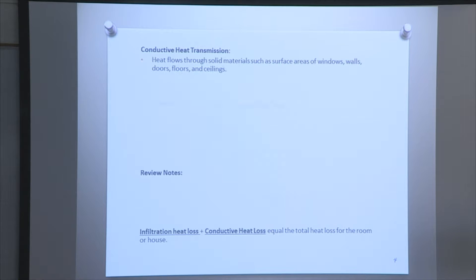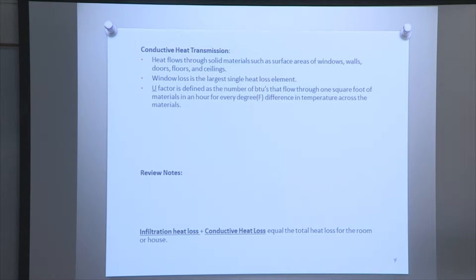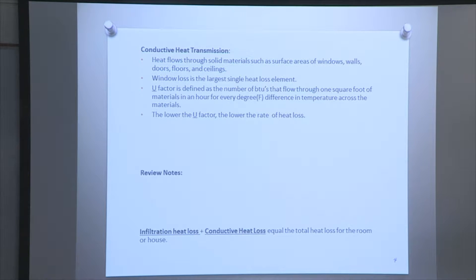Conductive heat transmission: heat flows through solid materials such as surface areas — windows, walls, doors, floors, or ceilings. Window loss is the largest single heat loss element. U-factor is defined as the number of BTUs that flows through one square foot of material in an hour for every degree Fahrenheit difference in temperature across the material. The lower the U-factor, the lower the rate of heat loss. Each penetration has its own U-factor.